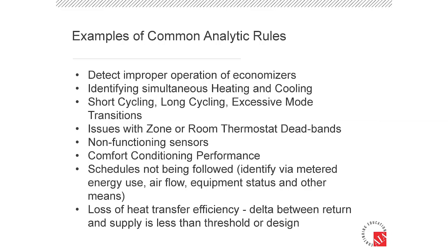Good example, loss of heat transfer efficiency. I expect 8 degrees of delta T across a coil. 6, 5, 4. Shoulder season day, everybody's comfortable, no alarms. What is that telling us? The light at the end of the tunnel is a train. You may be comfortable today, but you're not going to be as soon as the heat wave comes through.